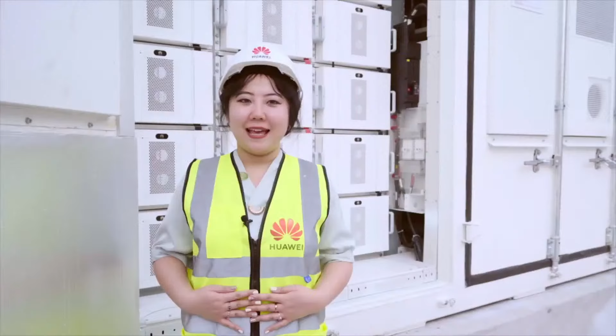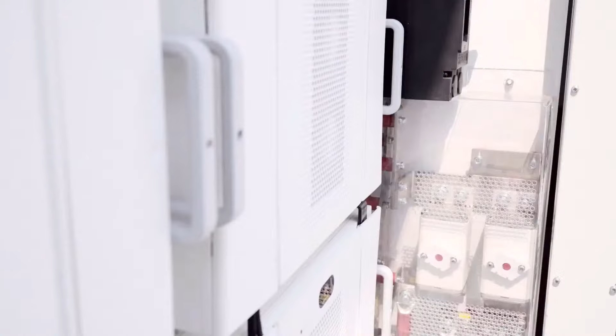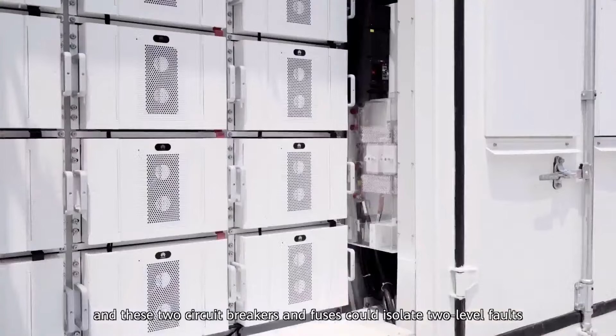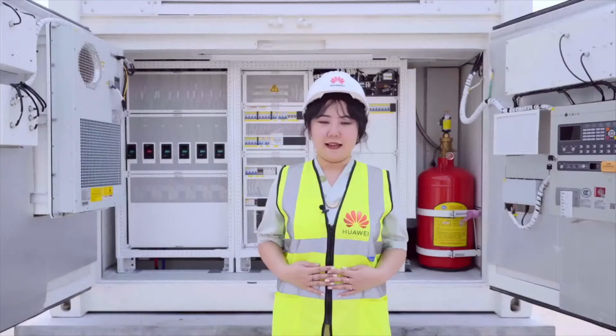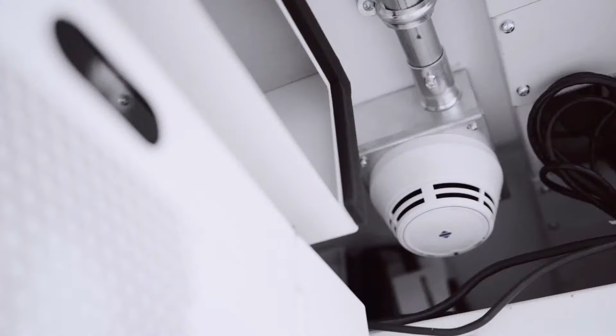Here are the battery packs — 16 320 Ah cells in each battery pack, with an internal battery pack optimizer. 21 battery packs are connected in series in a rack, and 6 battery racks are connected in parallel. The top right corner is equipped with a smart rack controller, and each battery rack connects to one DC-DC module. Down here is the DC box and fire extinguishing system. We'll show you how these technologies are applied in the system and achieve unique value for the project later.